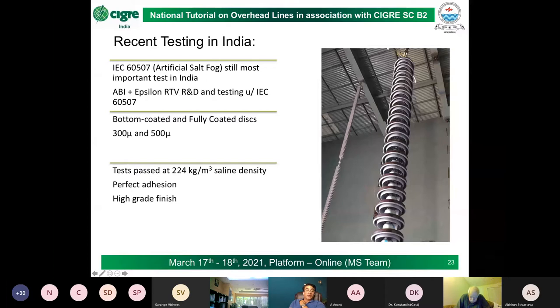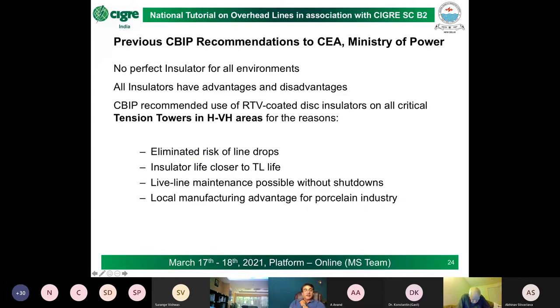Under his guidance, we did some testing on bottom-only coated insulators, fully coated insulators, at 300 microns, at 500 microns. And amazingly, we saw that even the undercoated insulators, just coated at 300 microns, hit this figure of 224 kg per cubic meter saline density. Everything worked very well with the salt fog. Adhesion was perfect in the end. The finish was perfect. So, all in all, we managed doing this in such a way that it did not need to modify the packaging of the insulator afterward, which is a remarkable thing, considering packaging is a major issue for coated insulators.